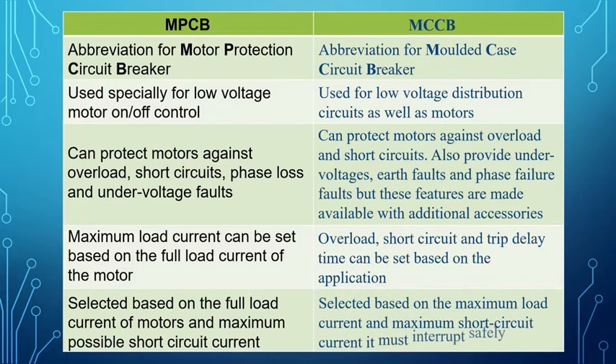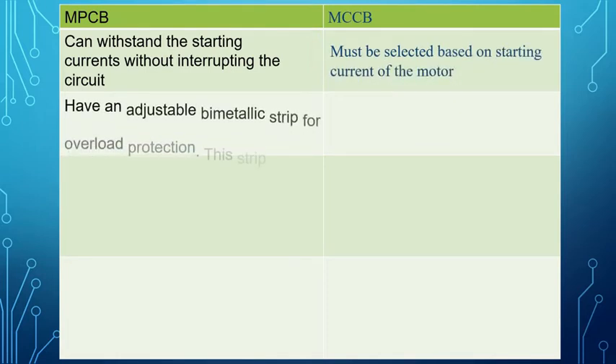MCCB is selected based on the maximum load current and maximum short circuit current it must interrupt safely. It must be selected based on starting current of the motor, while MPCB can withstand starting currents without interrupting the circuit. MPCB has an adjustable bimetallic strip for overload protection.